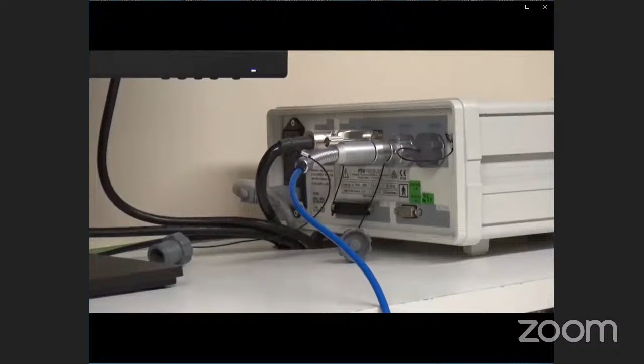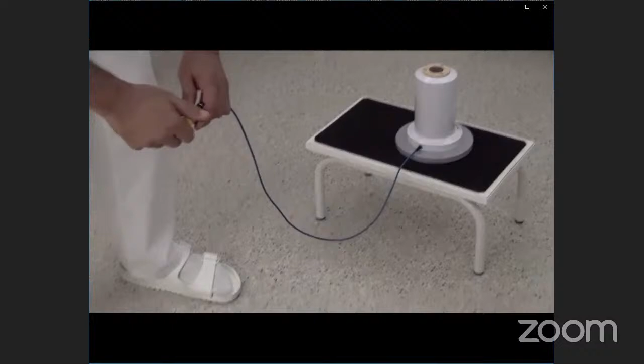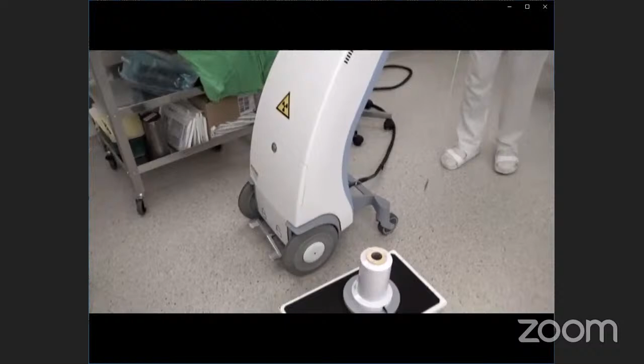The measuring cable outside the treatment room is connected to an electrometer. Inside the treatment room, the other end of the cable is connected to the well chamber. The chamber is positioned on a small stand in order to minimize the scattering from the floor. This is the afterloader unit.